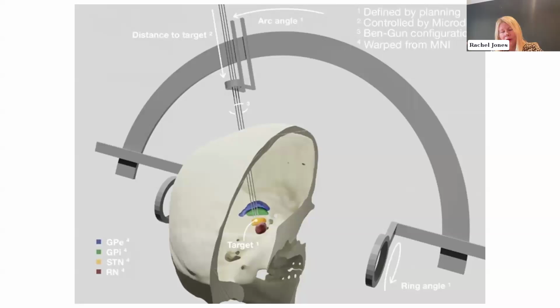Okay. So with that, you talked about a large magnet. What about an MRI? So say they were going for that kind of scan. What kind of precautions would they take? Okay, yeah, so it's a bit device specific. The newer devices have all been evaluated, and many of them have CE mark for being used in different MRIs at different intensities. So some of the new ones are compatible with what's called a 1.5 Tesla MRI, some with a 3 Tesla MRI. What that practically means is that they are safe to go in an MRI scanner, but often you should talk to your DBS service first because there are often some settings you would change first to try and minimize any risk to the battery.